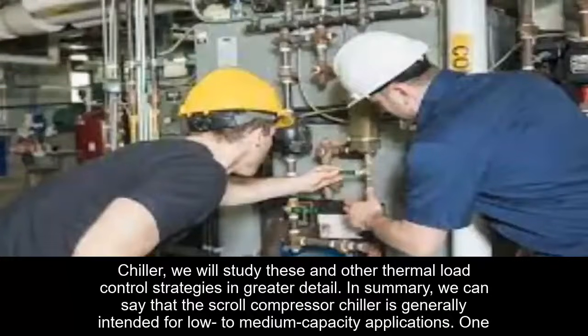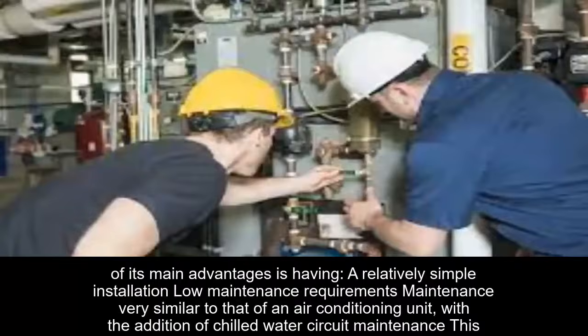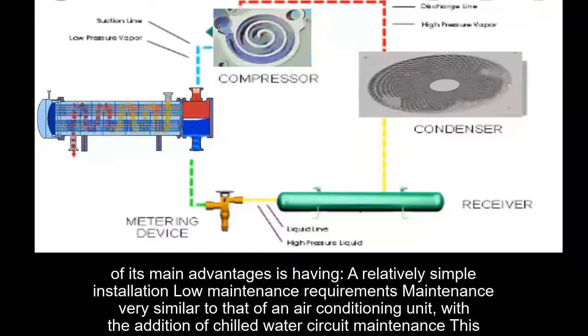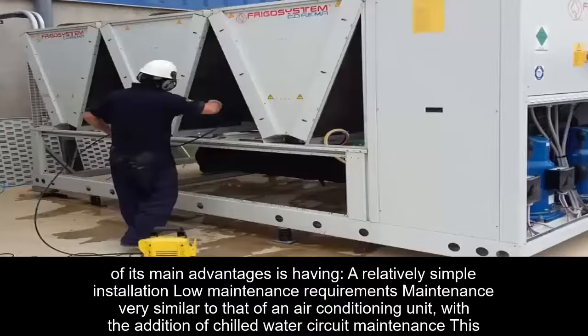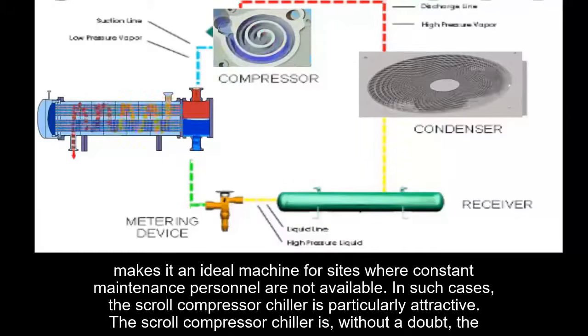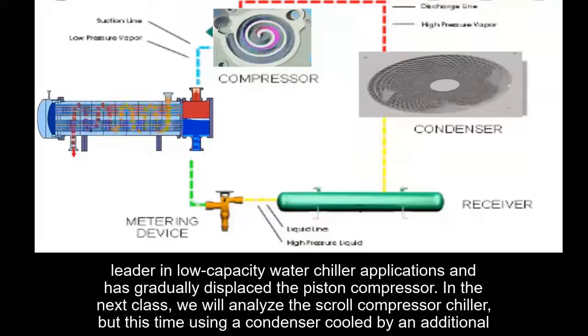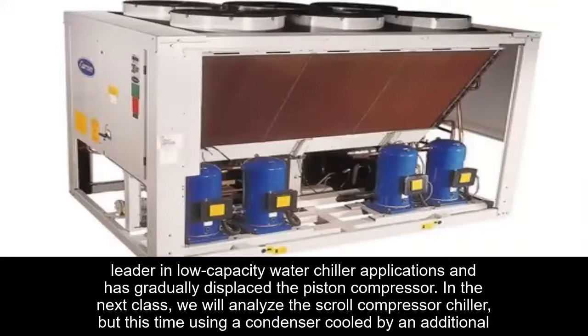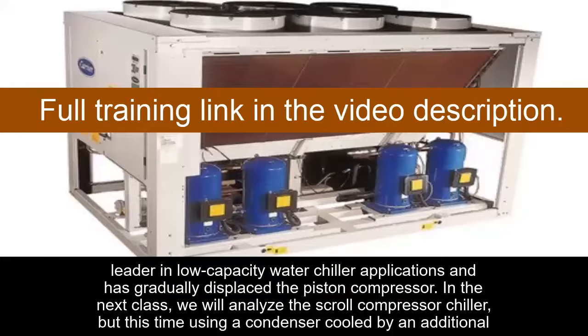In summary, we can say that the scroll compressor chiller is generally intended for low to medium capacity applications. One of its main advantages is having a relatively simple installation, low maintenance requirements, maintenance very similar to that of an air conditioning unit with the addition of chilled water circuit maintenance. This makes it an ideal machine for sites where constant maintenance personnel are not available. In such cases, the scroll compressor chiller is particularly attractive. The scroll compressor chiller is without a doubt the leader in low-capacity water chiller applications and has gradually displaced the piston compressor. In the next class, we will analyze the scroll compressor chiller, but in this case using a condenser cooled by an additional water circuit.